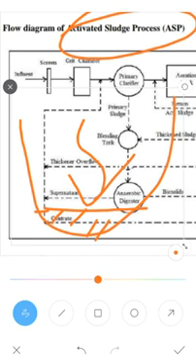The mixture of recycled sludge and sewage in the aeration tank is referred to as the mixed liquor. The recycling of sludge helps in the initial buildup of a high concentration of active microorganisms, which accelerates BOD removal.